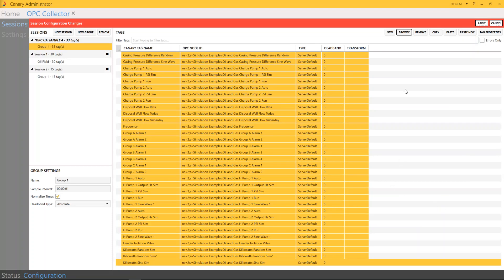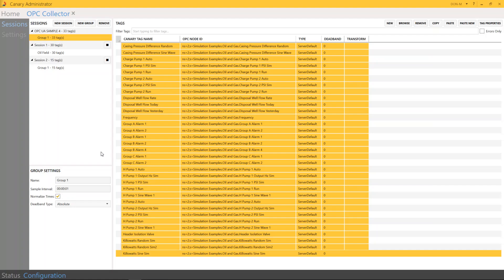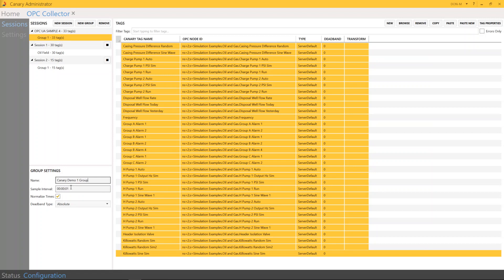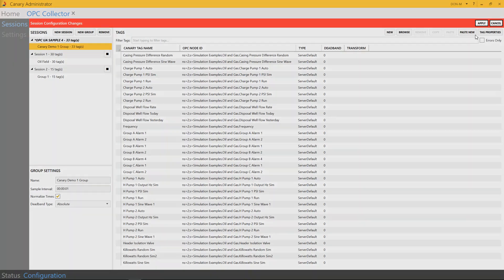And as you can see, the data tags have been moved over to the group, and I'm going to press Apply. You also have under the group settings the ability to change the name of the group. So I'm going to change this to Canary Demo 1 group. You also have a sample interval here that you can adjust, normalize timing, as well as a deadband type, which can either be absolute or percent. And I'm going to hit Apply now that these are here.